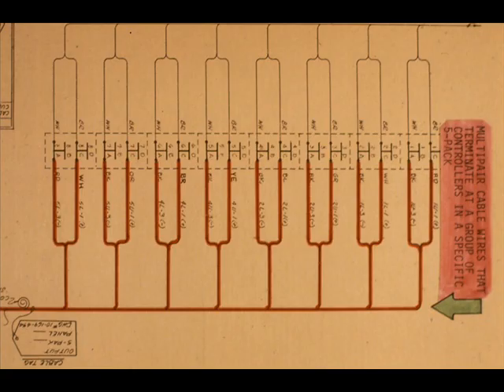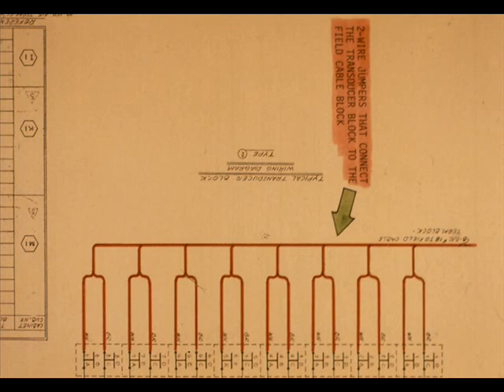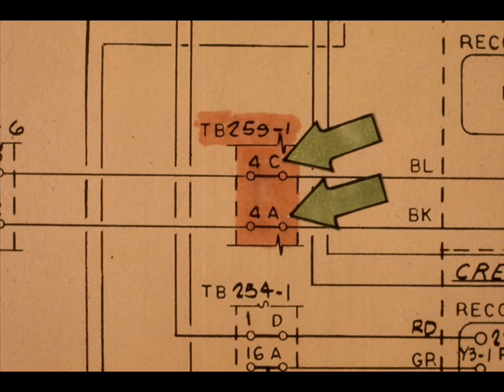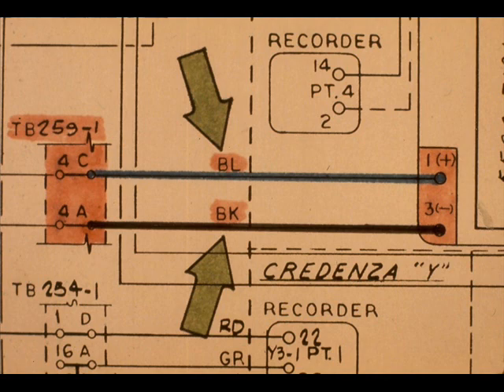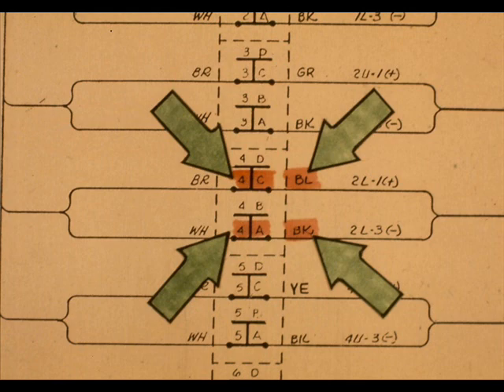The wires on the right are multi-pair cable wires that terminate at a group of controllers in a specific 5-pack. The wires on the left are two-wire jumpers that connect the transducer block to the field cable block. Look at the transducer block TB259-1. What terminals are used? Terminals 4C and 4A. What color wire pair is used? The blue-black pair. Check the transducer terminal drawing. Terminals 4C and 4A do terminate with the blue-black cable pair.